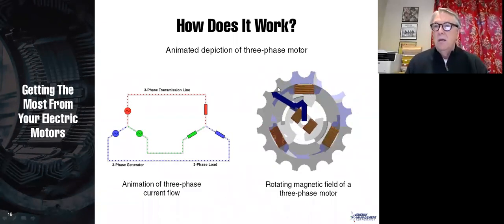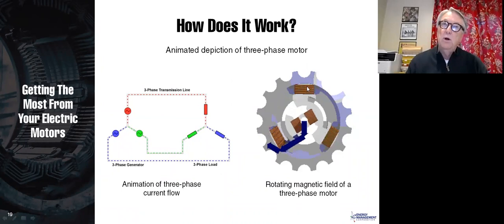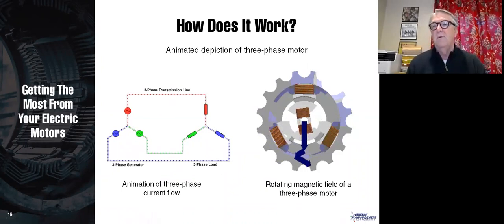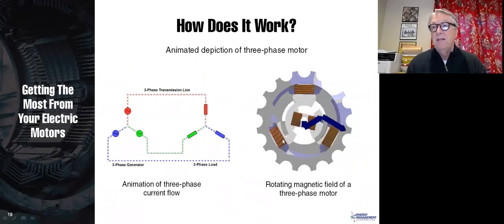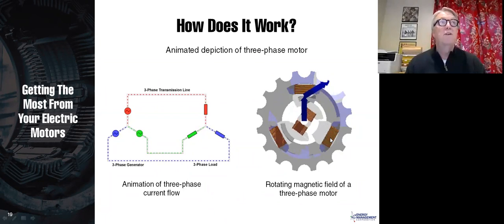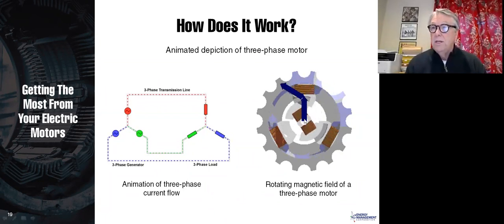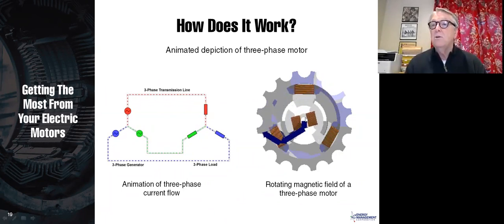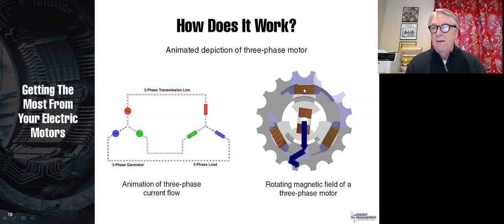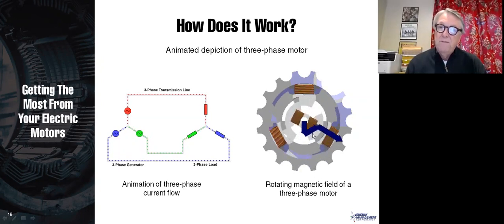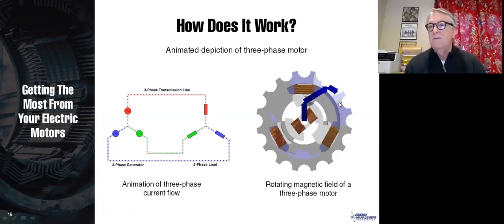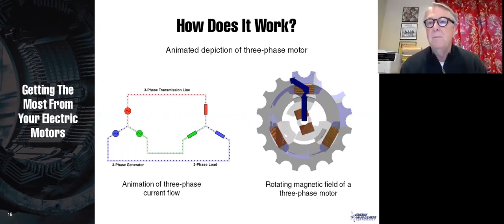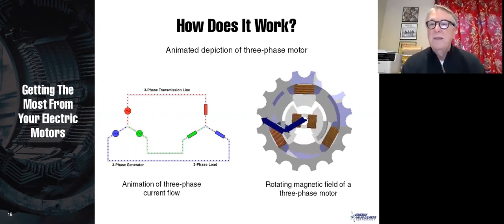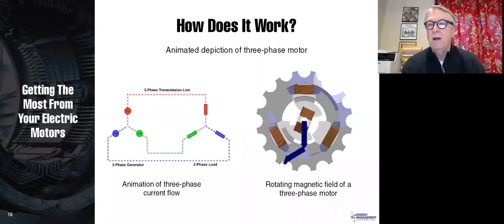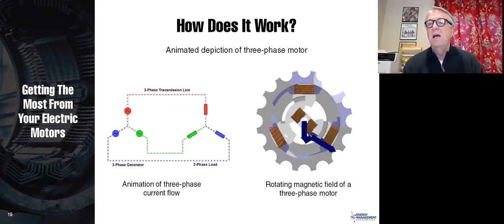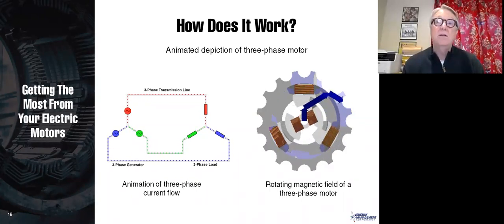This is an animation. Now you'll notice that this is A phase up here. We're only showing the positive side, but there would be a negative side in a real motor. Then over on the left, we have B phase and then C phase. And you'll notice that each of those phases is an AC sine wave. And so this vertical arrow is the flux or the magnetics that is created by A phase. This one that is aligned with B phase is created by B phase, and this one aligned with C phase is produced by the C phase electromagnet. But when you add them all together, notice that the sum total magnet always stays the same strength. That would be the length of the arrow from the middle to the outside. And instead of just going up and down, it actually goes around the motor.